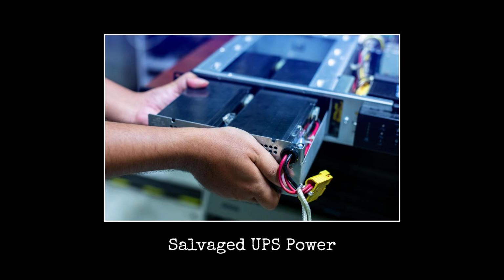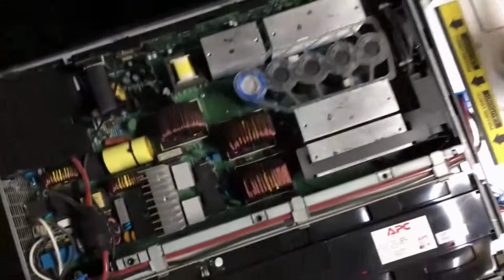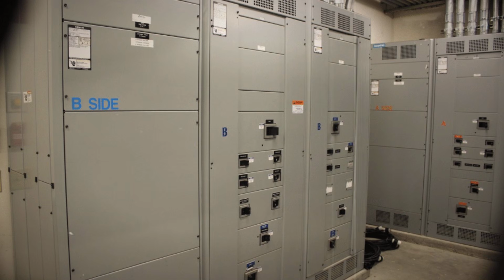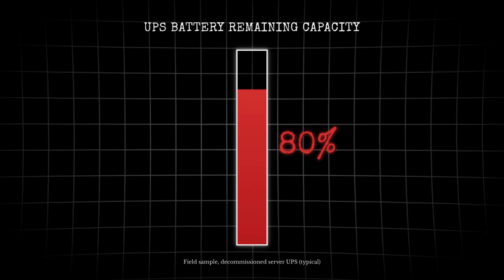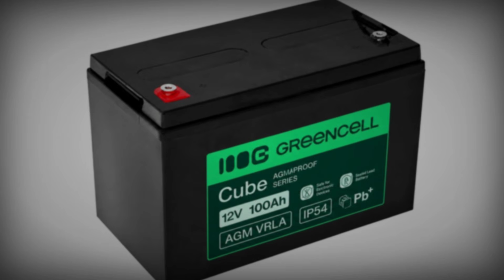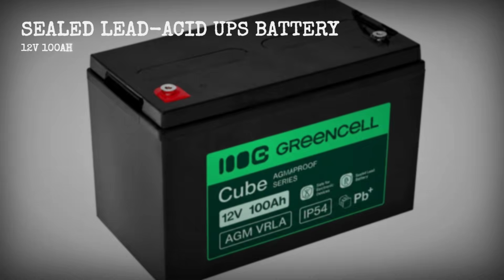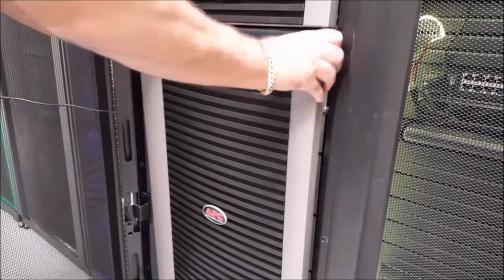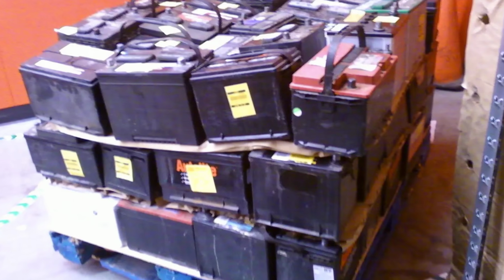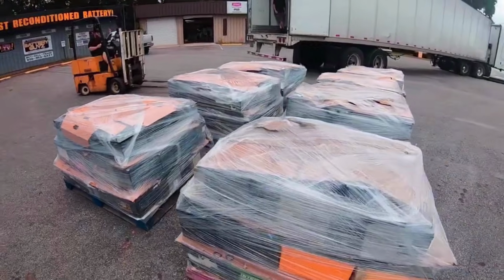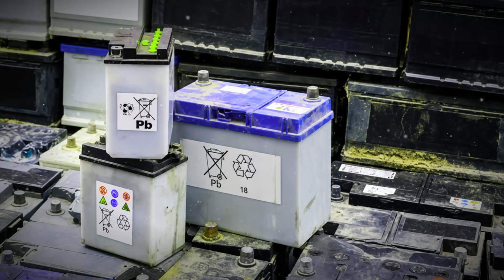Server rack UPS batteries are the easiest entry point. Data centers replace their uninterruptible power supply batteries on a fixed maintenance schedule, typically every 3 to 5 years, regardless of actual remaining capacity. A battery that's due for replacement in a server room might have 80% of its original capacity left. These are sealed lead-acid batteries, typically 12 volts, 100 amp hours. They pull out of the rack in standard sizes. They're clean, labeled, and often available in matched sets. Data centers and IT recyclers frequently give them away or sell them for under $20 each because disposal is the alternative. Not sexy, not lithium, but free or nearly free kilowatt-hours are free kilowatt-hours.